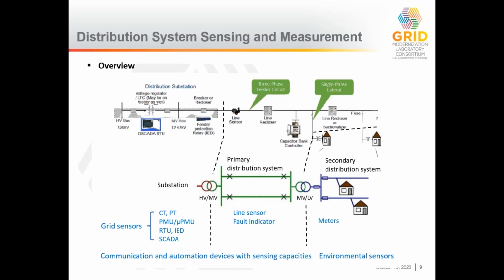In the actual primary distribution system, there are things to enable the types of voltage control and fault location I mentioned earlier, like line sensors that determine current flow or current spikes on the sensors. There are also fault indicators, where there can be conditions where even a field crew person can just see a light on a device sitting on a pole and know that there's something faulted on that line, so they know what to do or where to see it, because we still rely on a degree of visual interaction with these kinds of things.